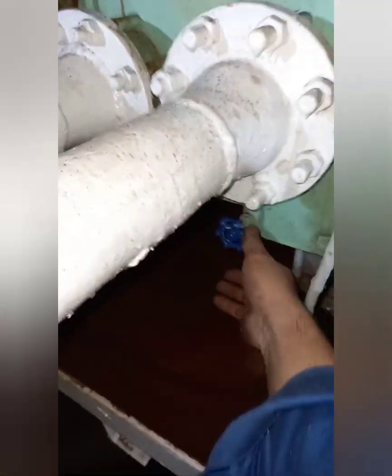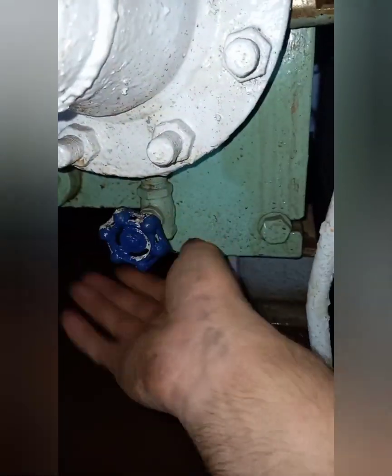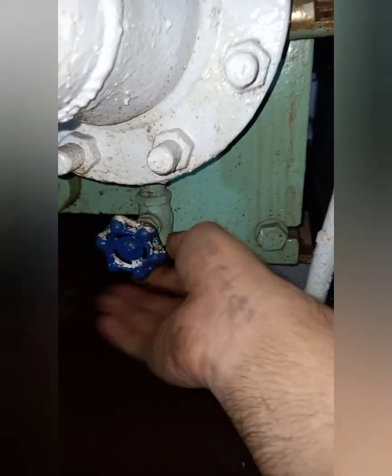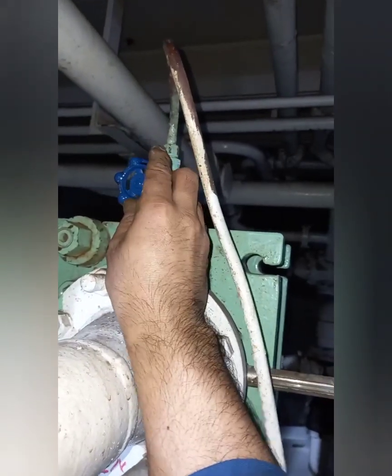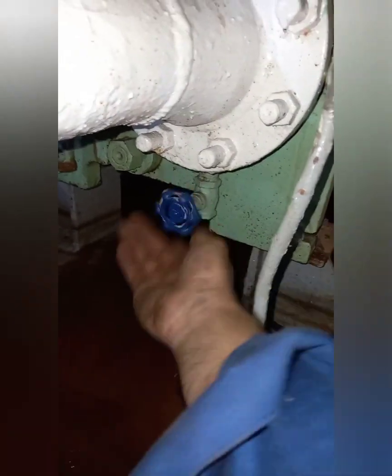Next, open the freshwater side drain valve at the bottom of the cooler. This is to check if there is leakage between the seawater side and the freshwater side of the cooler. There is no leakage found. Close the freshwater side drain valve.